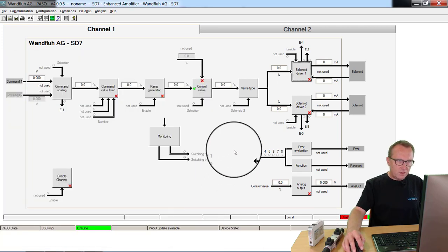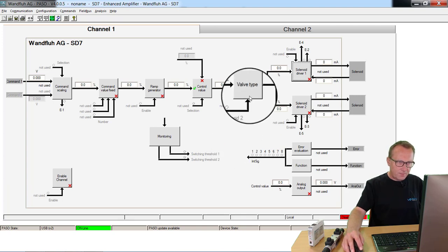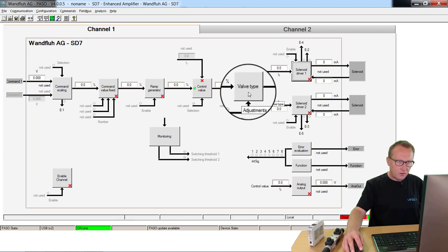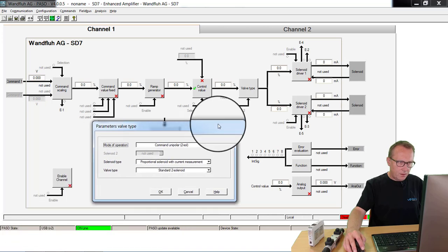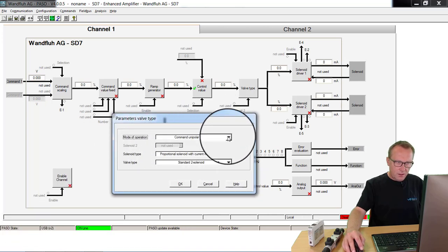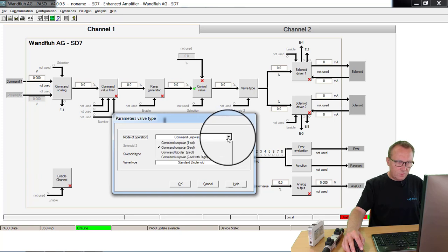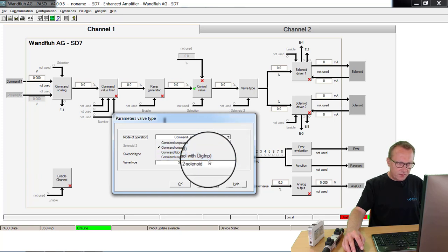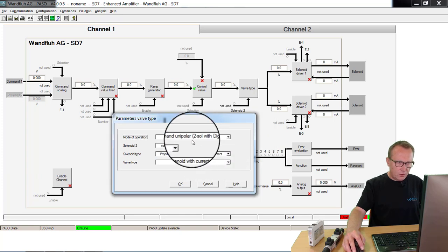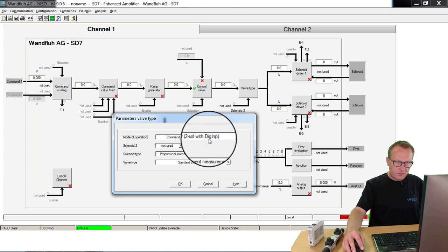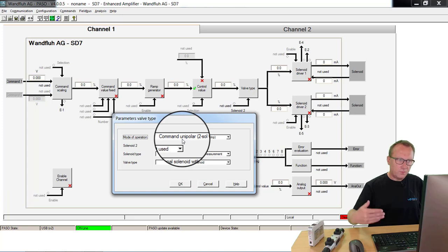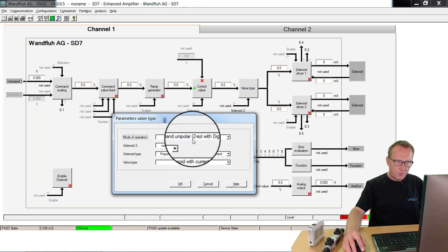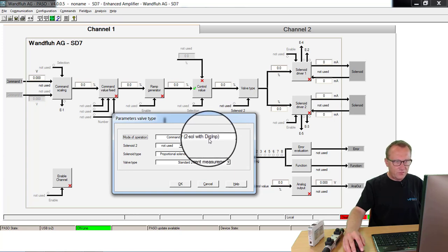We will start with the selection of the direction. We go to the valve type and we are using the parameter mode of operation. For our demo application, we need the command unipolar 2 solenoid with digital input. That means our command value is a value from zero to a positive value. We control two solenoids and the selection of the rotation we make with a digital input.